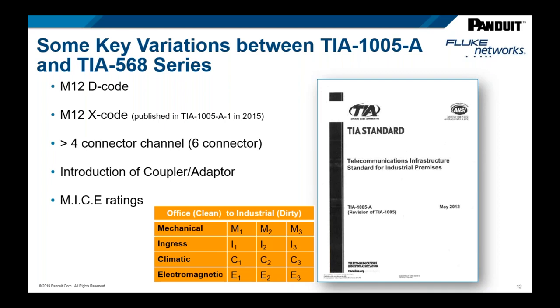What sets TIA-1005A apart from the commercial standard is recognizing the dynamics of the plant floor environment and the adoption of the MICE criteria. MICE is an acronym covering Mechanical, Ingress, Climate/Chemical, and Electromagnetic — things commonly evaluated by design engineers on the plant floor. The standard accommodates different deployment scenarios such as control panels and adjusts for those MICE criteria, recognizing the difference from the more static commercial environment.